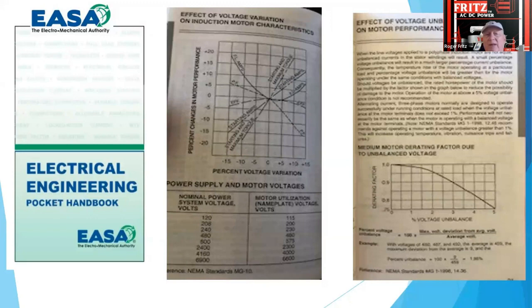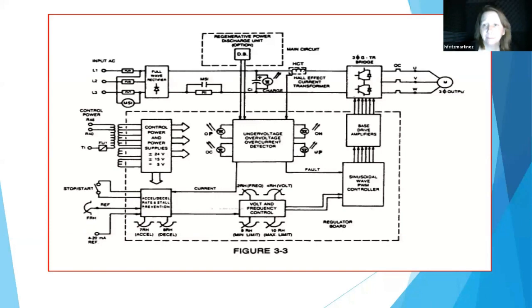We've done a lot of remote applications where they only have single-phase power, especially in the Midwest, and we're running 3-phase motors, up to 50, 75 horsepower, on single-phase input. And we're able to help the power company because it doesn't surge it. It brings it on softly. So, that helps. Was there a question, Heidi, in the chat? Do you read what that chat is? Or was that just somebody? Not that I see. Okay.